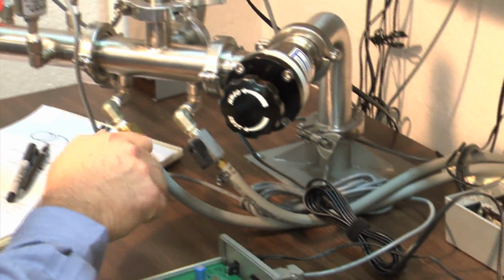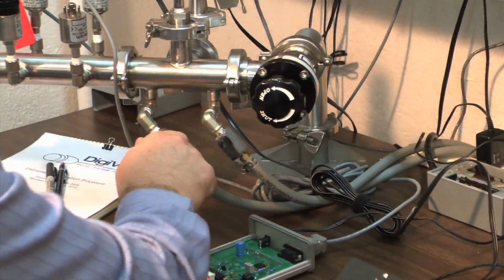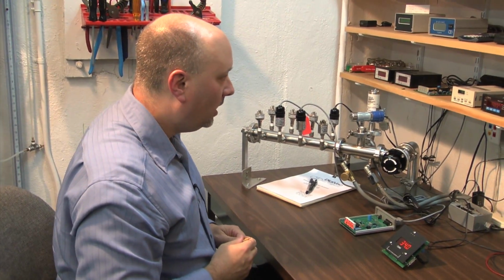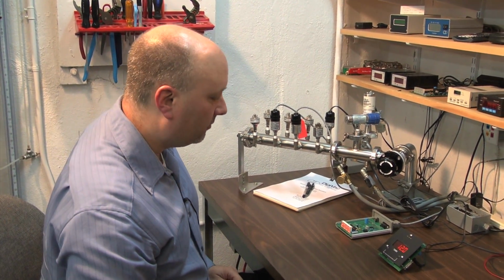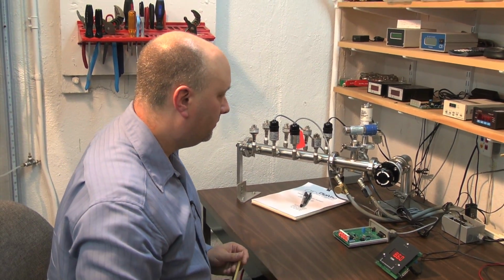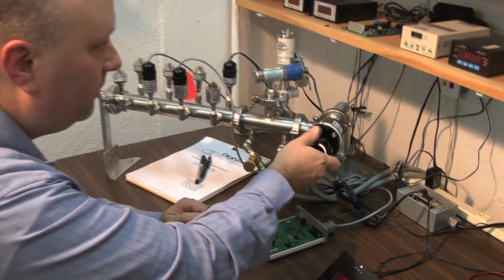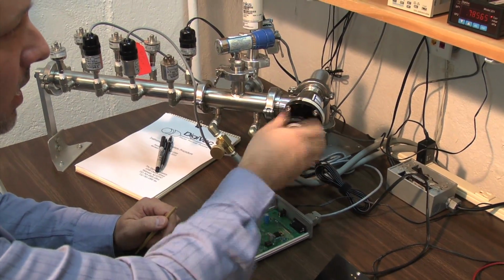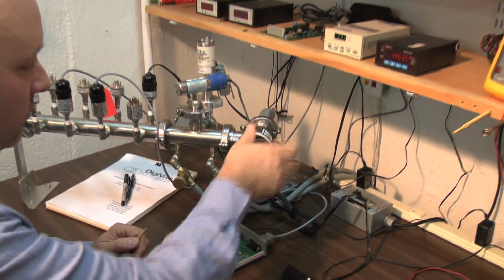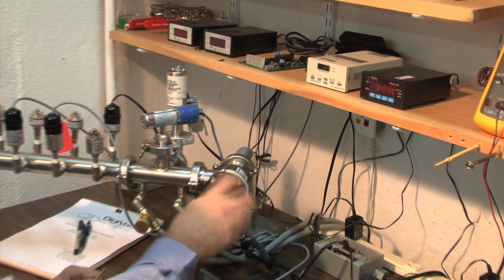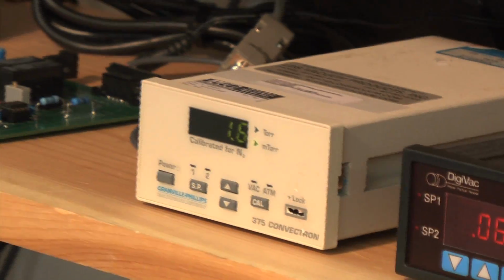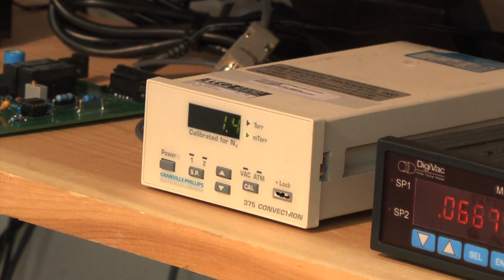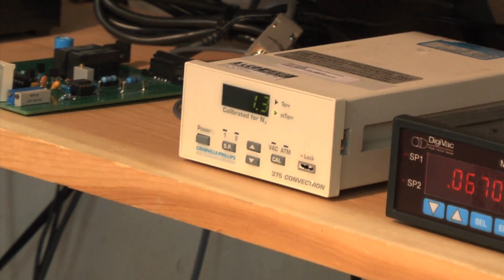Energize our roughing pump, pump our system down to the lowest achievable vacuum. Here at DigiVac, we can hit 10 to the negative third or 1 micron. Any pressure lower than 10 microns is acceptable for calibrating the bottom end of our 801W. Stop our roughing pump, open our diffusion pump. Watching our 375 convectron, we would like to see the pressure reach 1 millitorr or lower. Pressure is approaching 1 millitorr. We're currently at 1.4, 1.3.